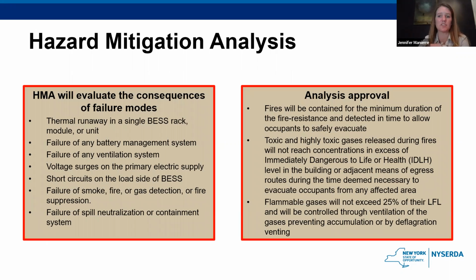Okay, the hazard mitigation analysis is a requirement for what we've defined as tier 2 systems. So larger systems, anything over 600 kilowatt hours. So we're talking medium, large scale commercial on up. They will all have to do a hazard mitigation analysis per the requirements in the code. This is probably done by an engineering firm, and this basically just allows the permitting authority, the community, to determine the best approach on what to do if there is a failure.